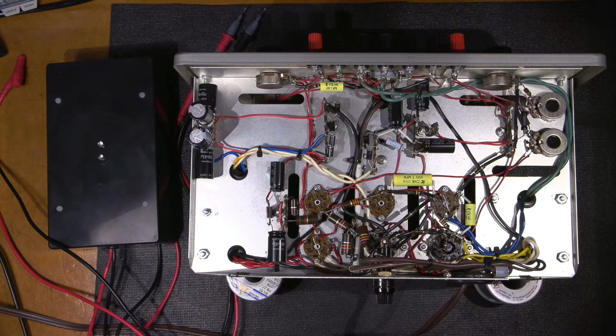Now, a lot of people feel comfortable putting shorting bars across capacitors, especially large electrolytics, and it's not a bad idea, but the only problem is that if you forget to take one of those shorting bars off before you power the unit up again, you're going to destroy the unit. You're going to blow all the diodes out of it, take the fuse out, and all sorts of things like that. Any kind of short, low impedance or low resistance connection is going to make them become jumpers. So you want to be very sure about that. If you're going to use the shorting bar technique, you have to really make sure that you've removed those things, double, triple check, almost have a checklist beside you.